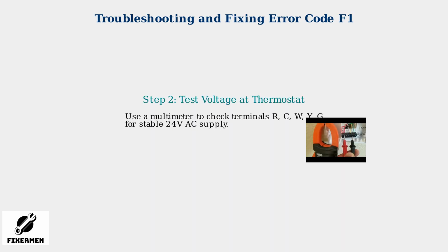Begin by checking all electrical connections to ensure they are secure. Loose or faulty connections are a common cause of the F1 error. Use a multimeter to test the voltage at the thermostat terminals R, C, W, Y, and G. Confirm you have a stable 24-volt AC supply. Fluctuations indicate wiring or transformer issues.